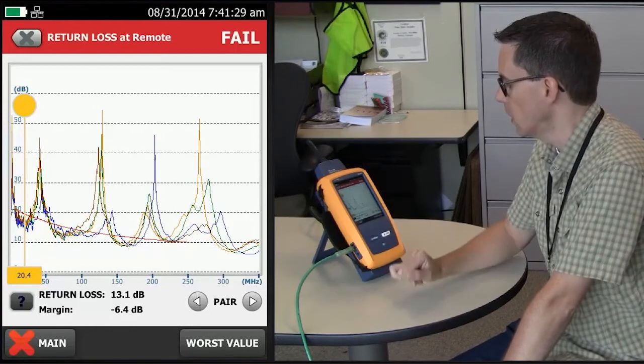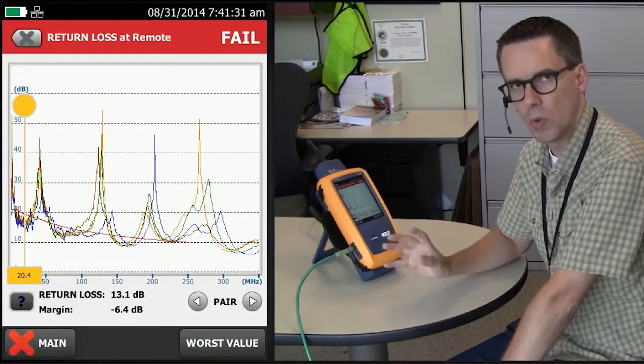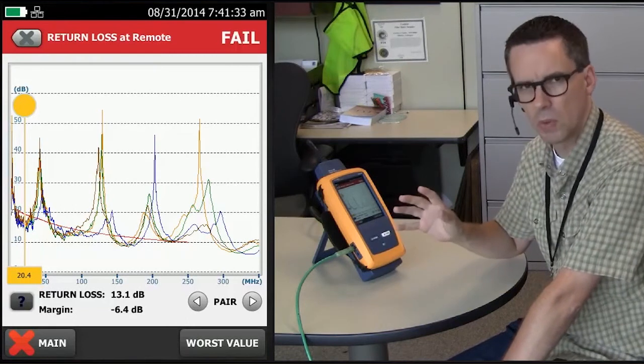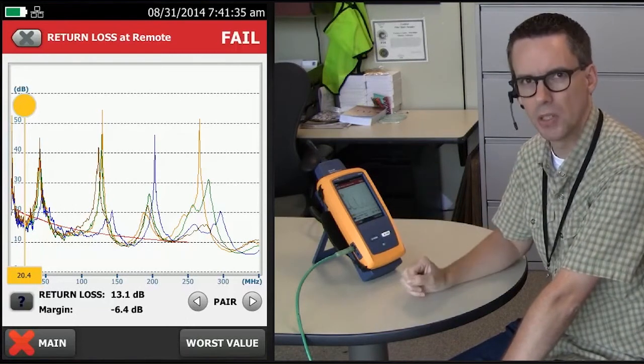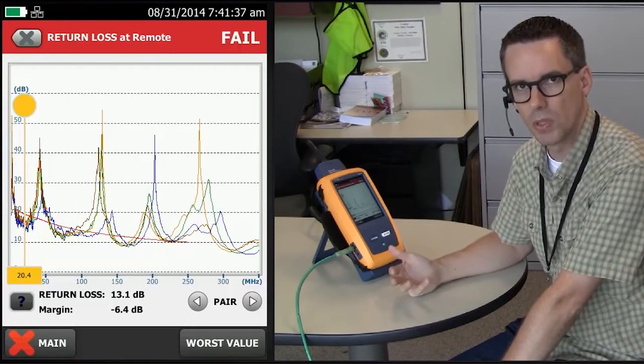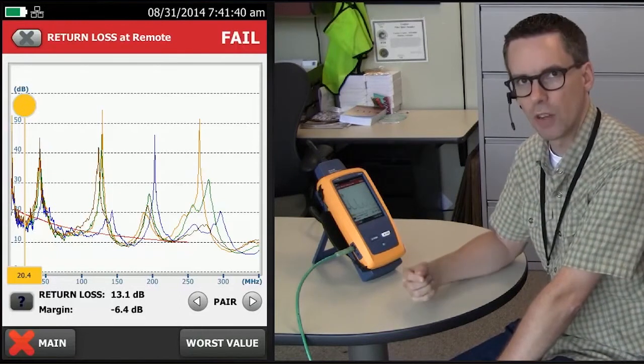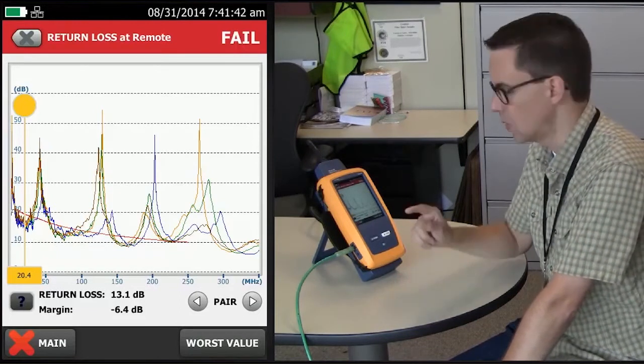Now, from a previous video, I said there was a general rule that if it failed at the lower frequencies, below about 50 MHz, then you could assume that there was a cable issue. But you've also got to check for a DC contact resistance issue.